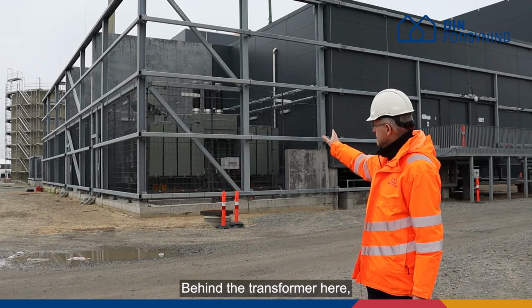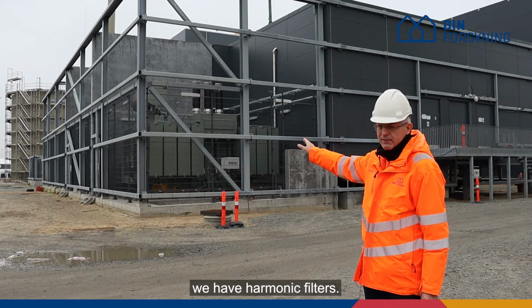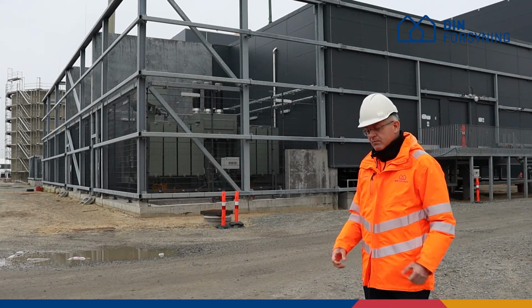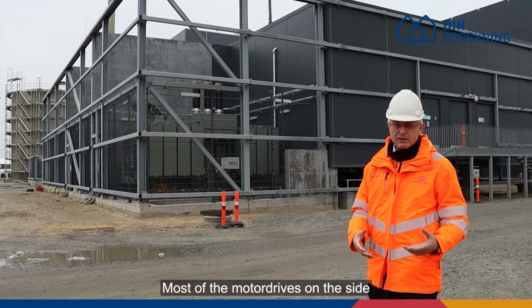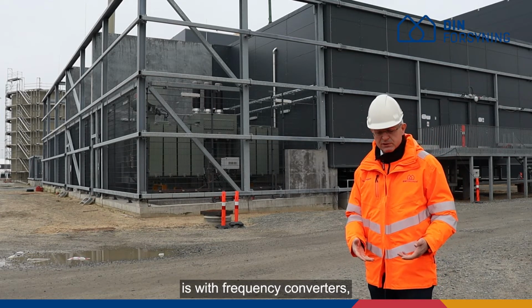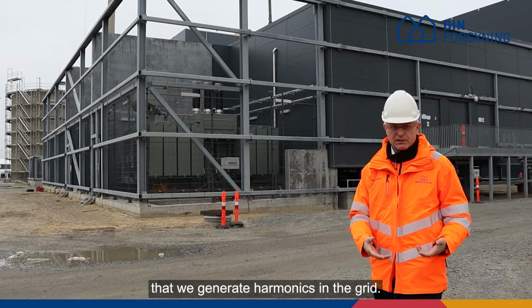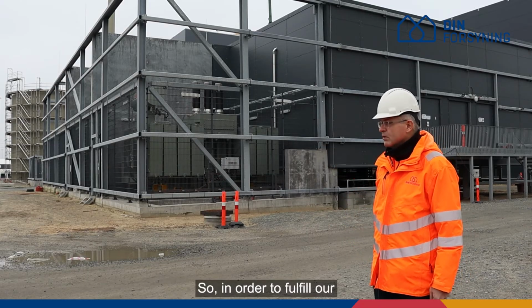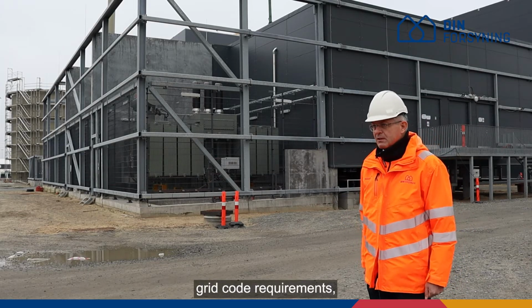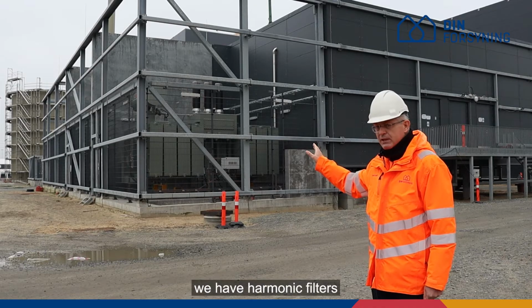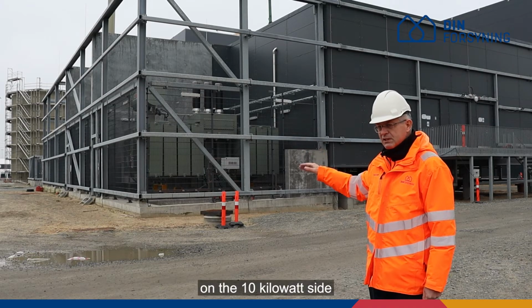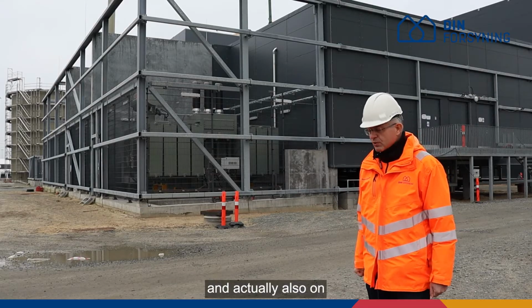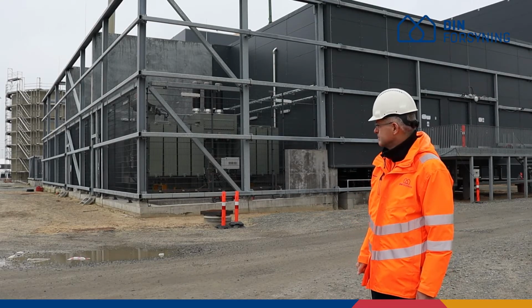Behind the transformer here we have harmonic filters. Most of the motor drives on the site are with frequency converters, which means that we generate harmonics in the grid. So in order to fulfill our grid code requirements, we have harmonic filters on the 10 kilovolt side and actually also on the low voltage sides of the system.